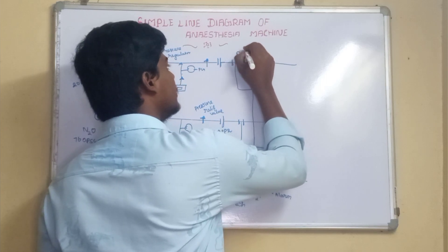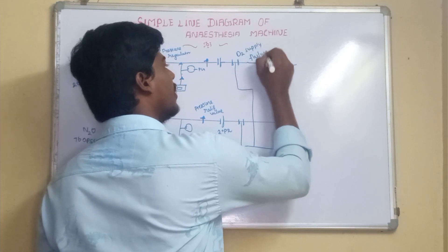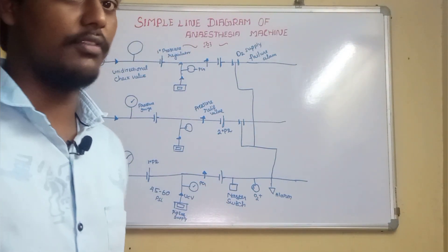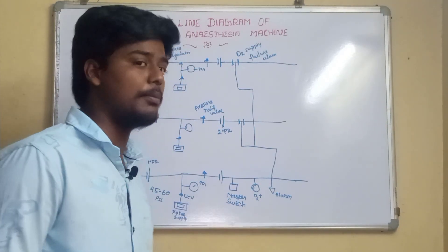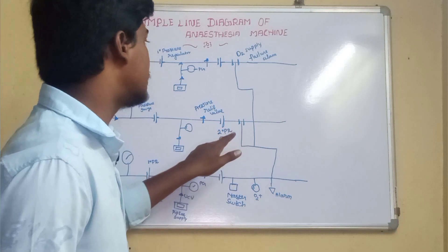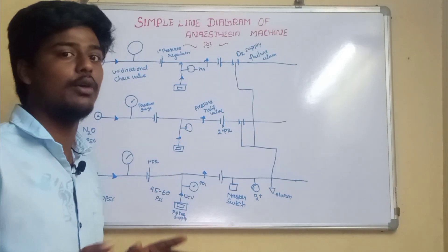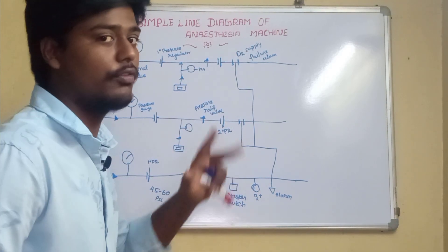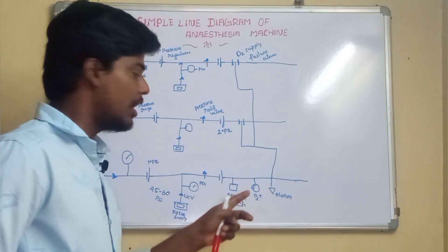The oxygen supply failure alarm activates when oxygen pressure is reduced below the manufacturer level. This prevents the delivery of a hypoxic gas mixture to the patient. When the oxygen supply fails, the alarm also cuts down the other gases — air and nitrous oxide — as a safety measure. This is one of the key hypoxic guard and safety features of the anesthesia machine.